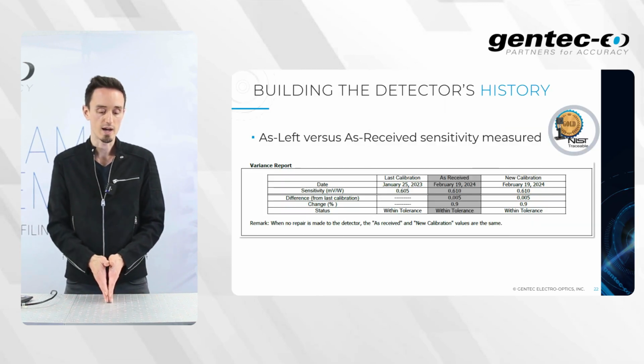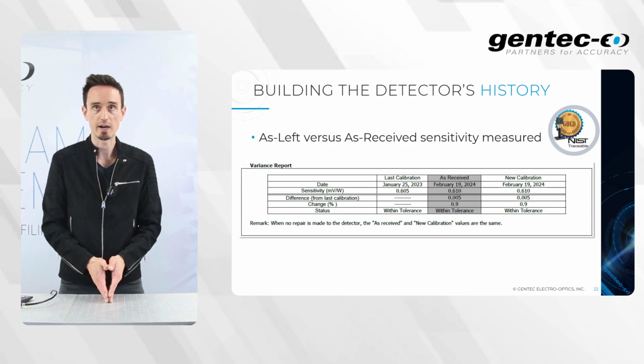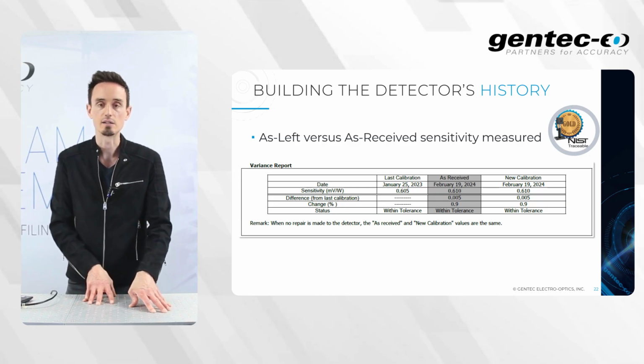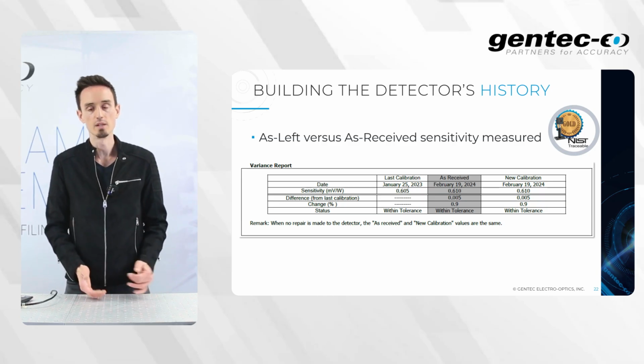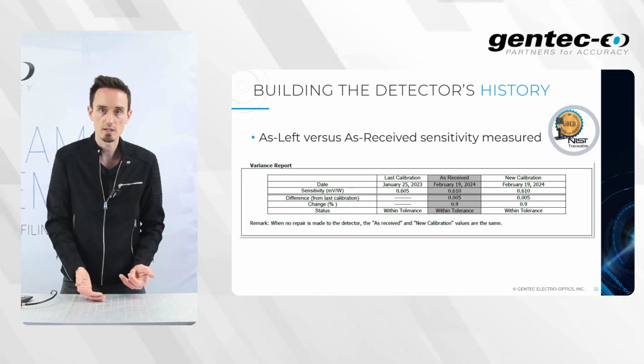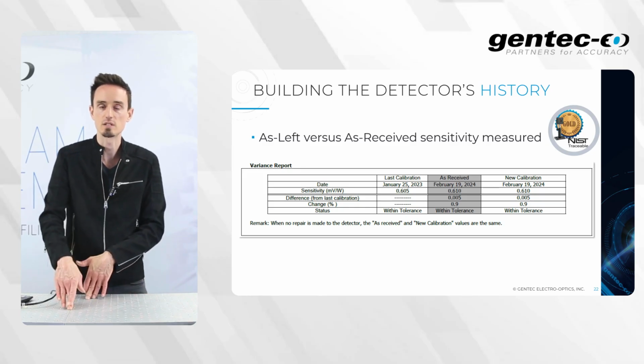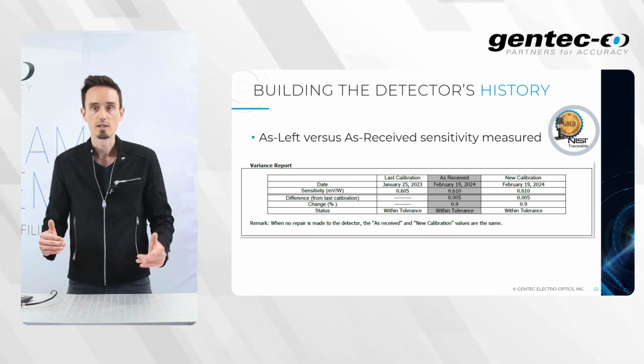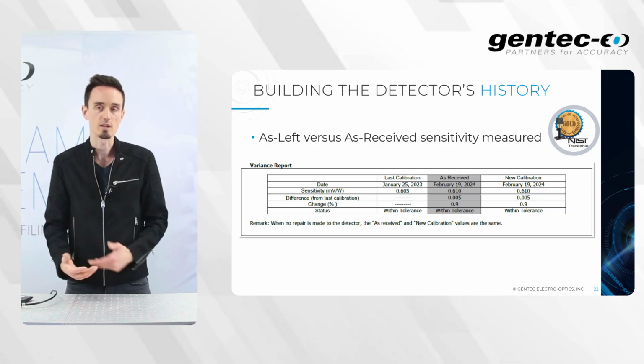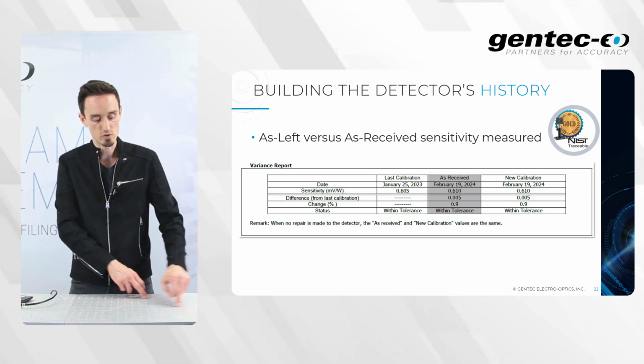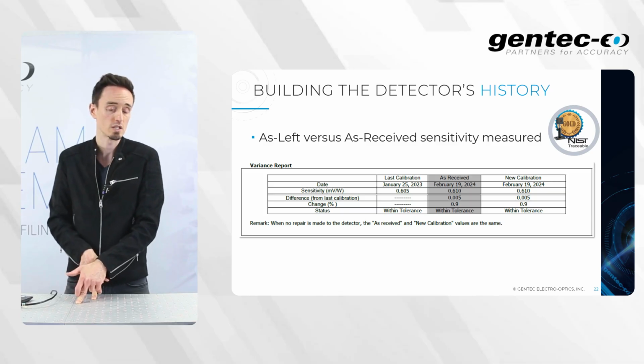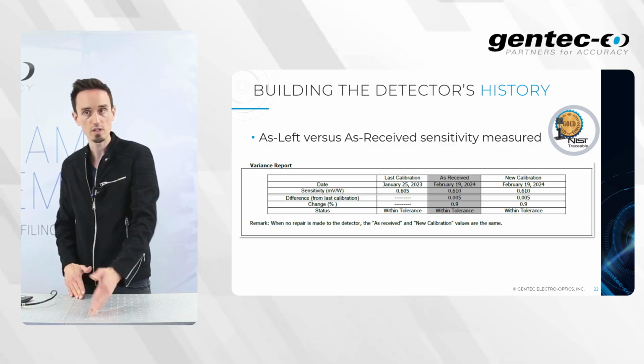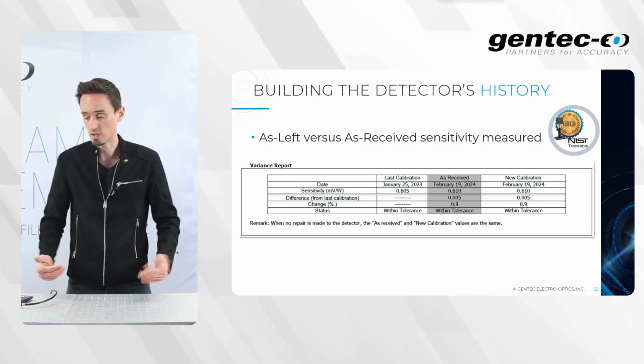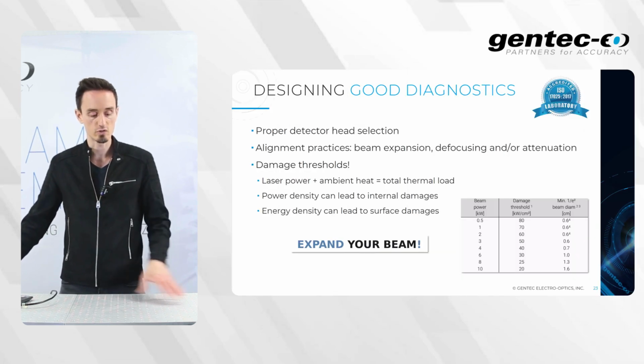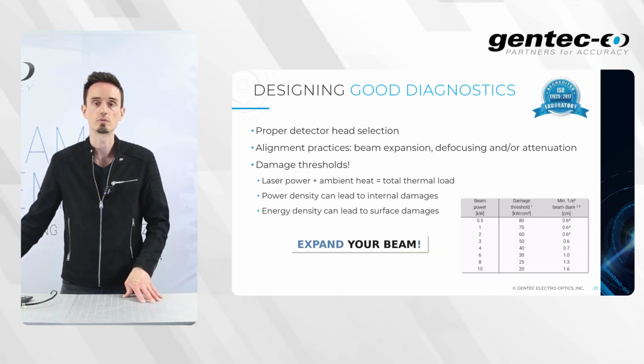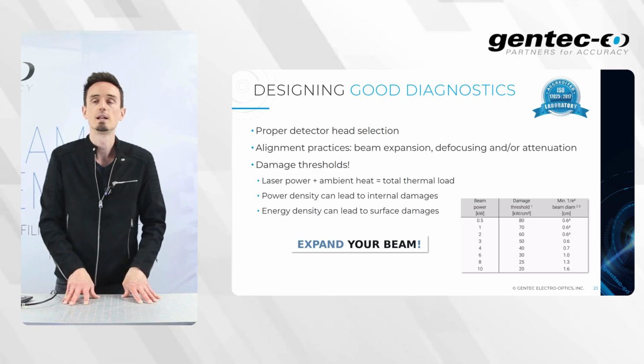And if we're considering recalibration and repair, the key idea here is to build the detector's history. When the detector is received, recalibrated, we do an as left versus as received sensitivity measurement, and we gather all this data again to see how the sensitivity has been drifting over time, to potentially advise on how to use the detector differently, or how to potentially change the detector for a given application. And all this data is recorded and made available to the users to build the detector's history.